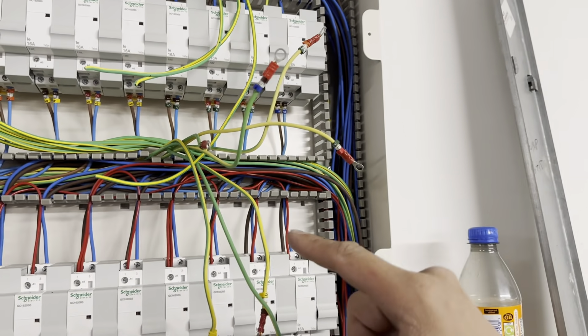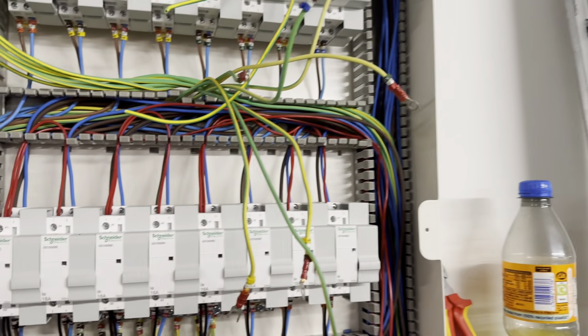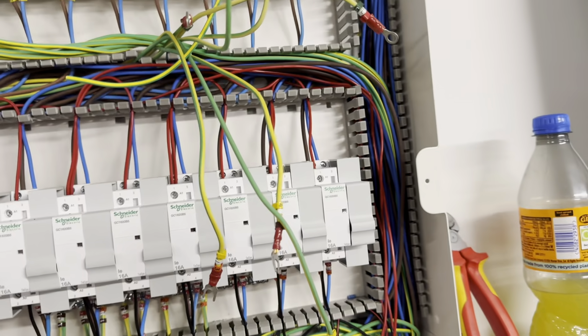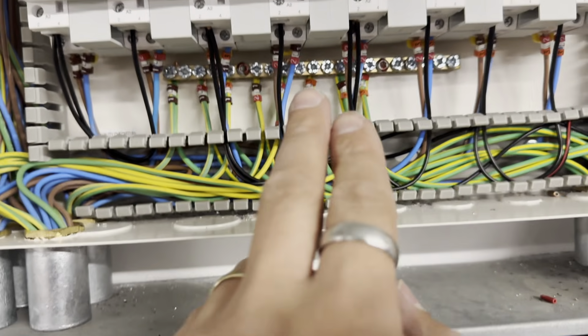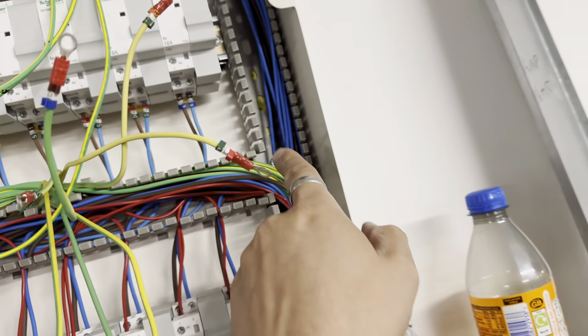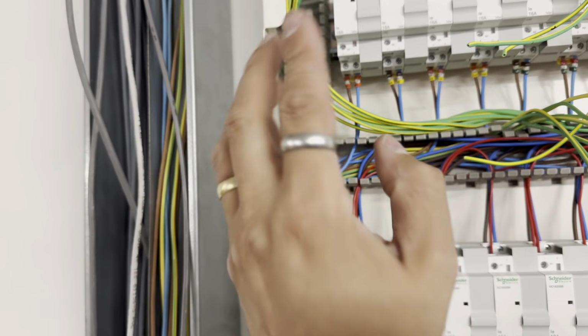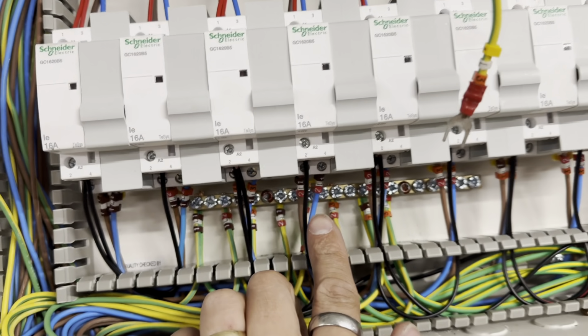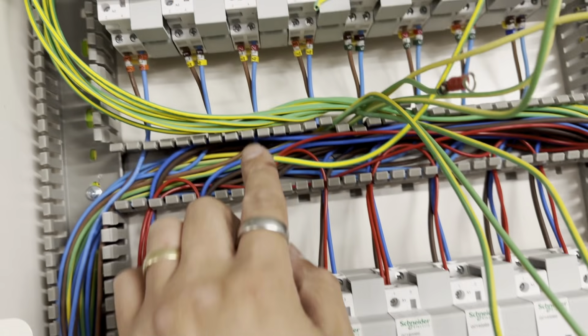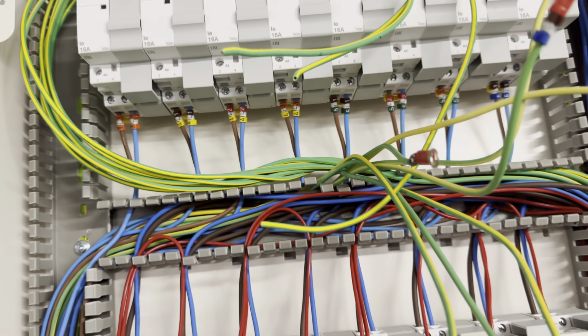We're going to have a series of transformers in a second panel identical to this one next to it, and I'll go through how that all works once I've mounted it. What I've done is moved this earth bar. Previously they come with an earth bar mounted there and one mounted there, but I've removed both. One is mounted here for this row of contactors, and the second one is going to get mounted here.